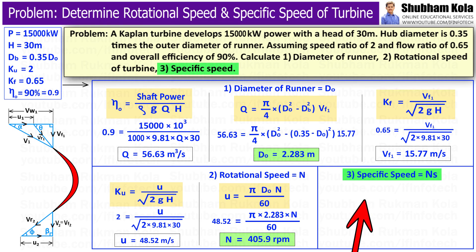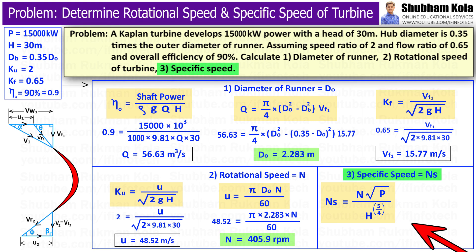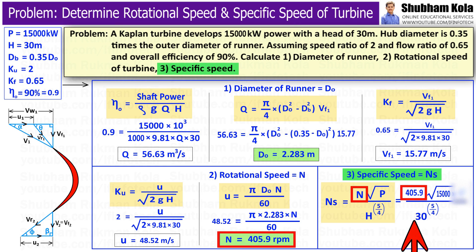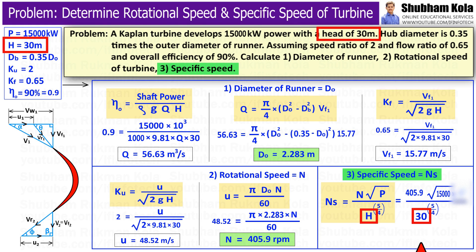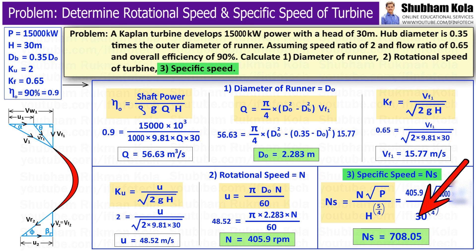To calculate specific speed, we use the specific speed formula with shaft power, the calculated speed N, and head of 30 meters. Substituting all these values, we get specific speed equal to 708.05.